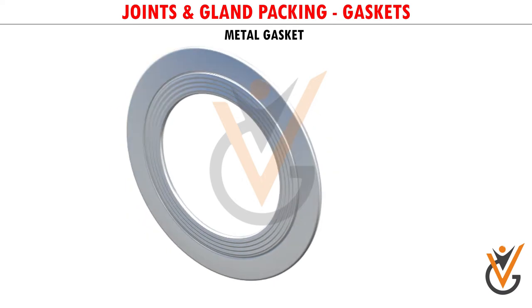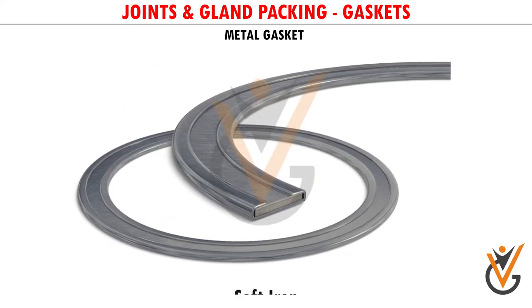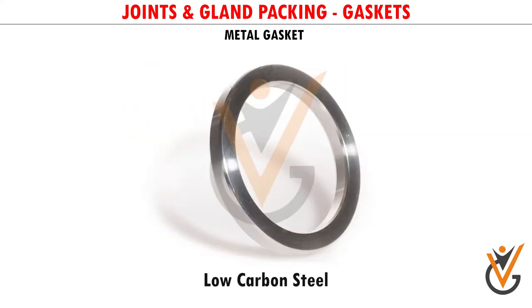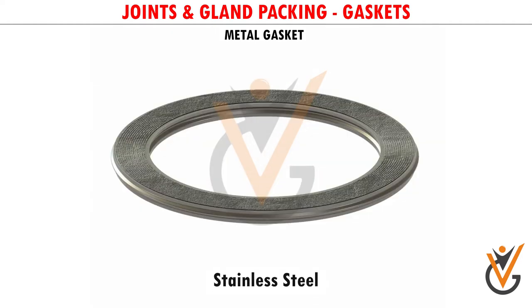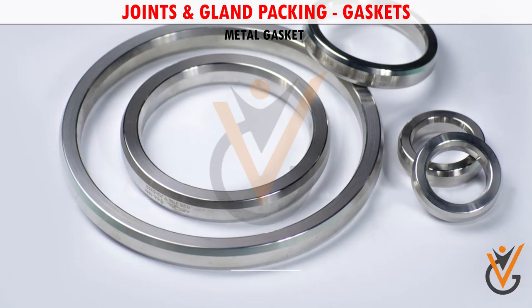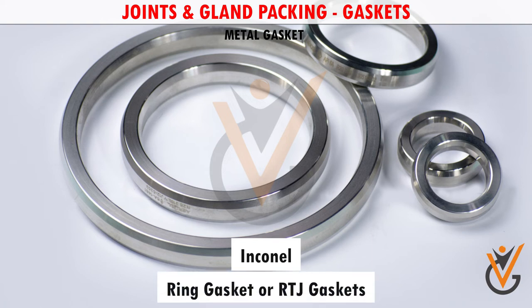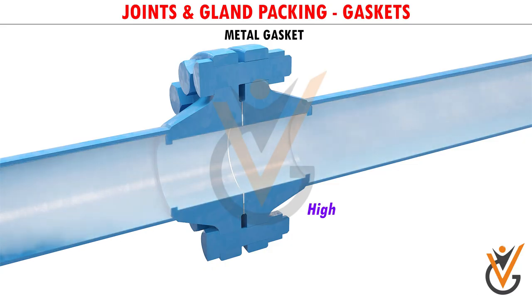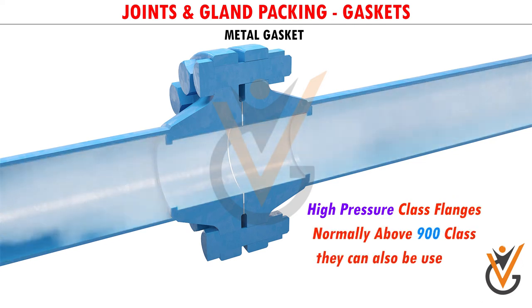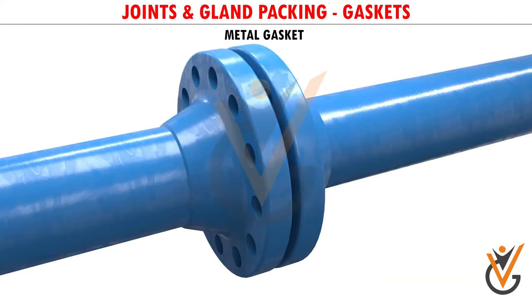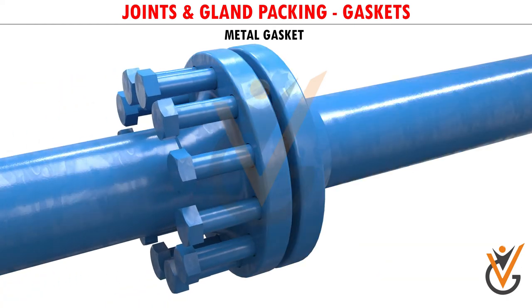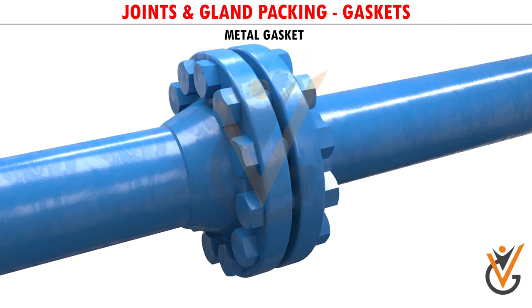Metal gaskets. Metal gaskets are manufactured from materials such as soft iron, low carbon steel, stainless steel, monel, and inconel. These gaskets are also known as ring gaskets or RTJ gaskets. Metallic gaskets are used in high pressure class flanges, normally above 900 class, and can also be used for high temperature. High tension bolting is required when using metallic gaskets. They are very robust and the most costly.